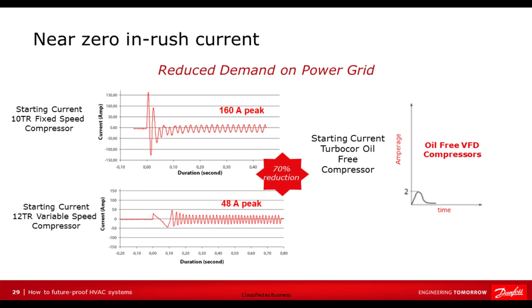In comparison, the starting amps on a fixed speed compressor is reduced through variable speed by up to 70%. The Danfoss Turbocor compressor offers a lower inrush current of less than 2 amps starting amp. Soft starting compressors avoid torque surges, which also prevent higher mechanical stresses, which in turn results in lower service costs and decreased wear. This lower inrush current also helps save fixed costs charged by utilities, peak current calculations, and reduces mains and power backup loads.